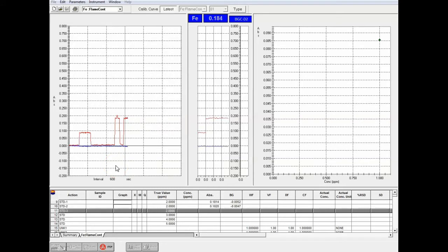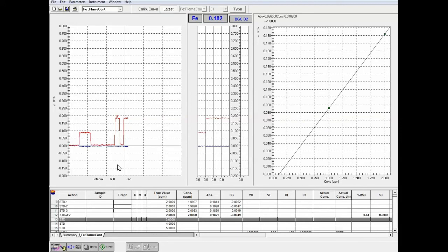Again, it's taking 3 measurements and giving us an average. So here we are. This was our 2 ppm. You can see that the machine took 3 readings and gave us an average. Now that we have 2 points, it also starts to plot our calibration curve. So here's our line so far. You have a perfect straight line so far because we only have 2 points. Here's our 1 ppm, there's our 2 ppm. You can see it also gives us the equation for the line and the R² value. Right now it's at 1, of course, because we only have 2 points. We want that to stay as close to 1 as possible. So let's run the rest of the standards, and then we'll come back and look at the graph again.